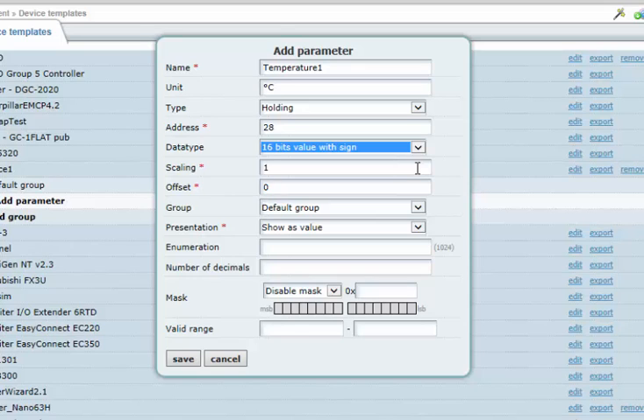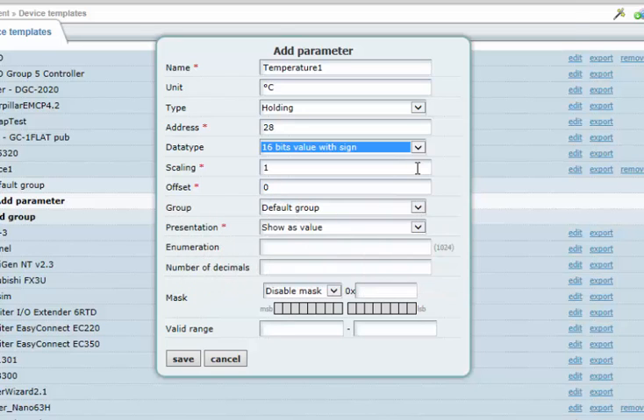One way of modifying values is to use scaling. A scaling value is basically another value, which is then used to divide the original value by. A value will be divided by the scaling value when it is read from the register, or, in the other direction, multiplied by the scaling factor when writing to the register.